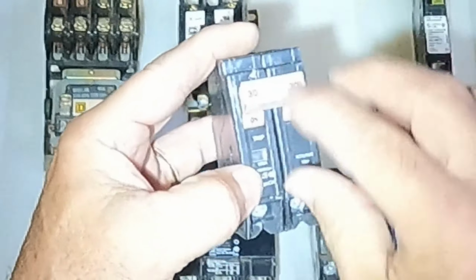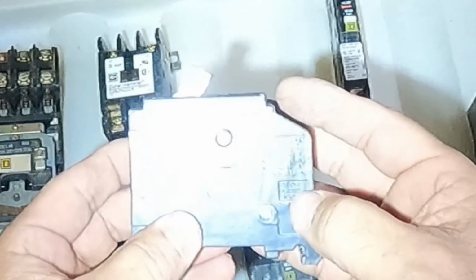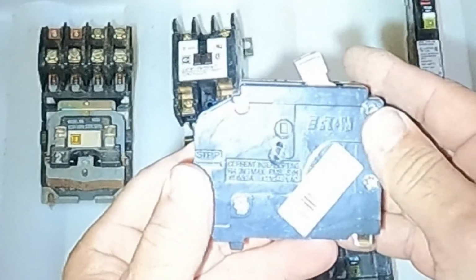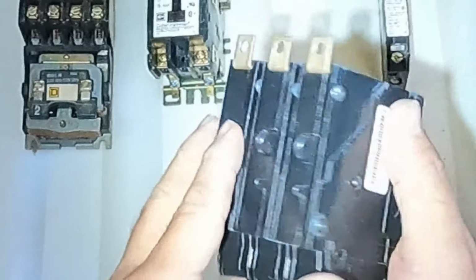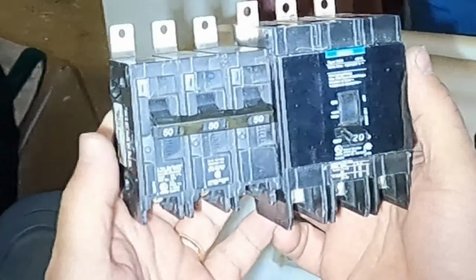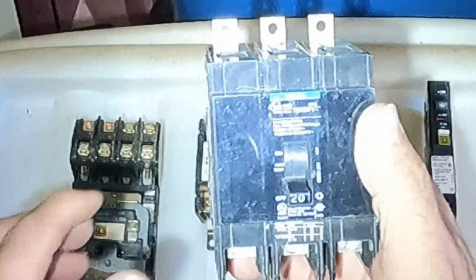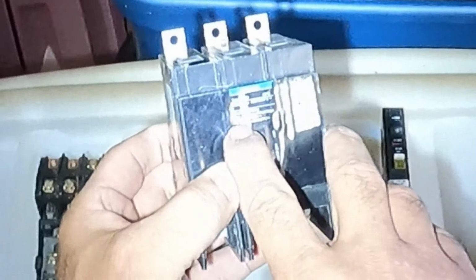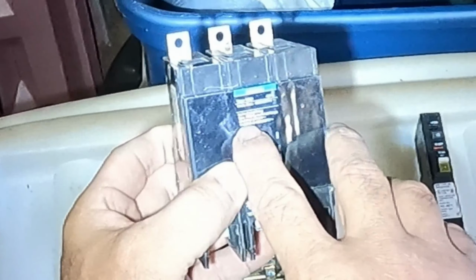What about this 2-pole Cutler Hammer, newer style, tan handle, 10 KAIC, which is nice. It's got the little window in it to show you if it's tripped. Tells you wire size. Again, no. Only AC. So let's jump to one that I know is... This one's not either. So here's another Siemens. This is a commercial 480 volt breaker. You could see this is a 120/240 volt breaker, and this is a 480 volt rated breaker. And it clearly says that at 240 volt, it's a 65 KAIC, and at 480, it's 14, but it has nothing showing DC. So this you can't use either.